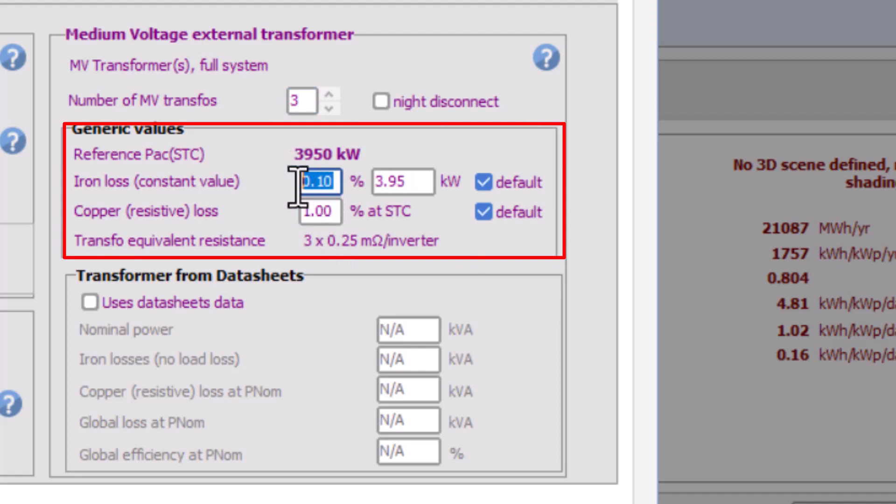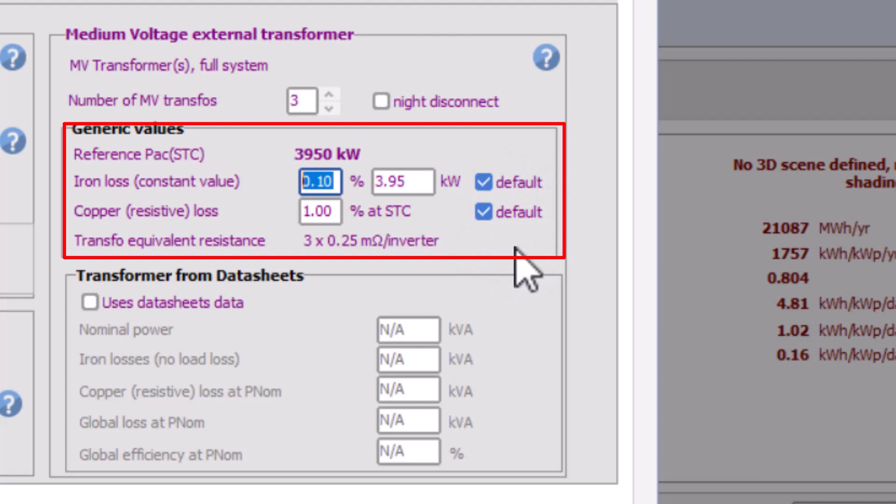And also you can set the number of MV transformers in your system. So you can set the transformer power loss details in two ways. First, just put the default values for iron loss and copper loss by checking the default box option. PVsyst suggests by default 0.1 percent for constant iron loss and 1 percent resistive loss, which is correct in almost all the cases for MV transformers.